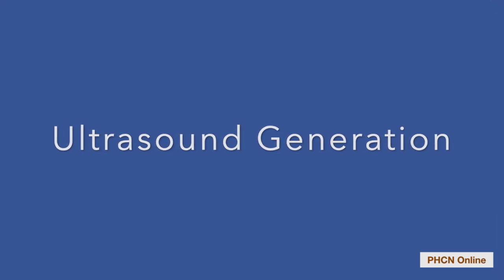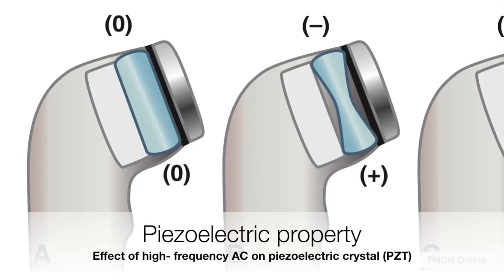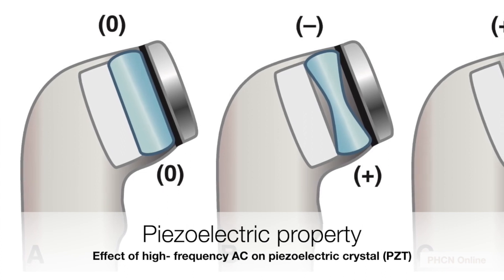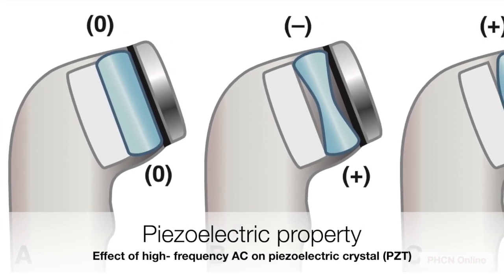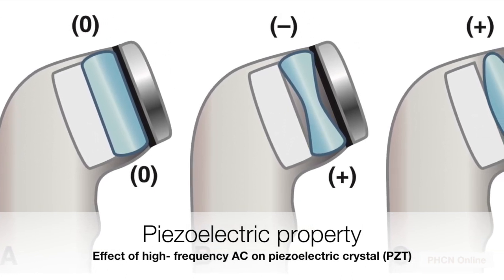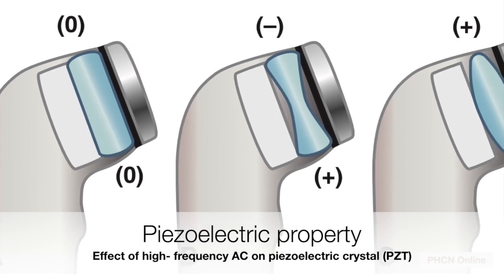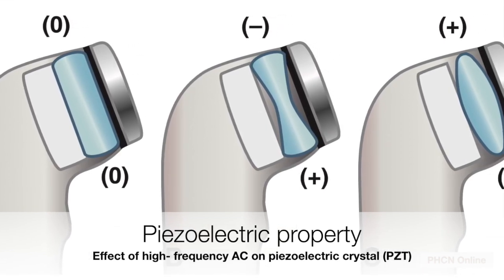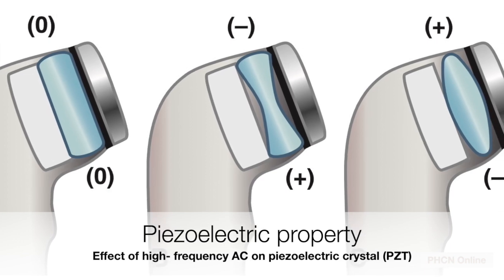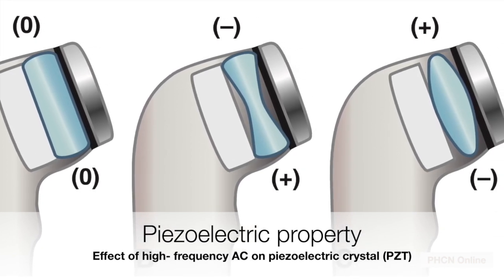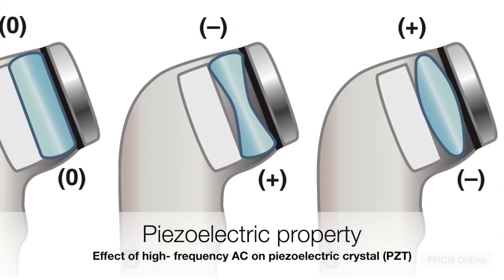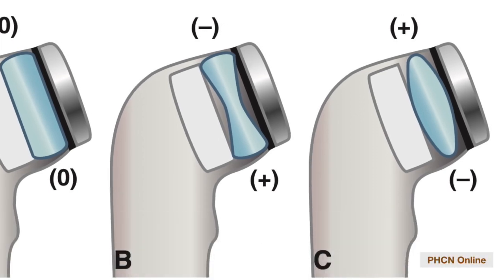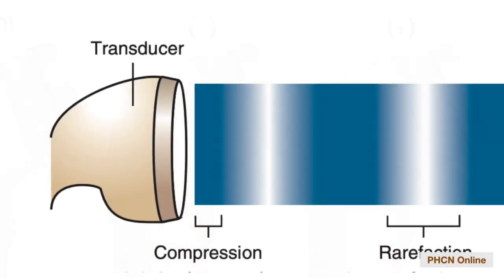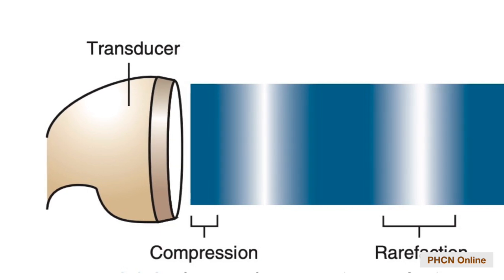Generation of ultrasound. Ultrasound is generated by applying a high-frequency alternating electrical current to the crystal in the transducer of an ultrasound unit. The crystal is made of a material with piezoelectric properties, causing it to respond to the alternating current by expanding and contracting at the same frequency at which the current changes polarity.